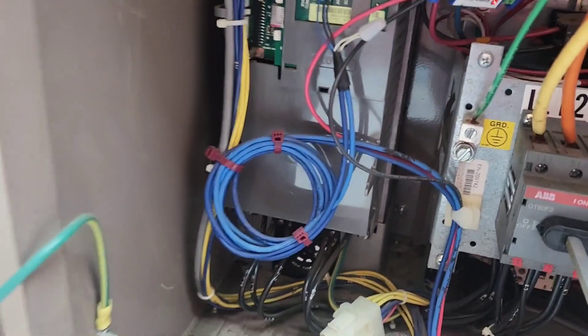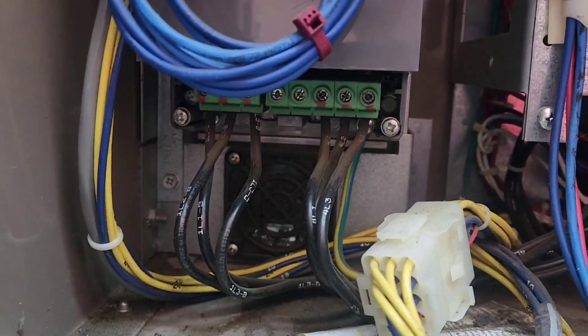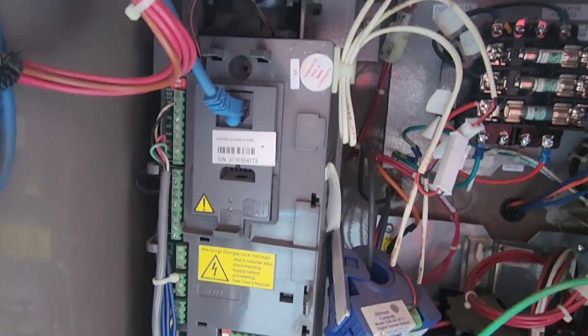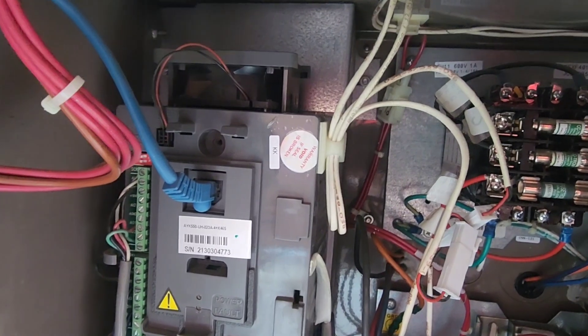Inside here with this particular drive, there's a total of two fans. You've got one right back there, and you have another one that is on the top of the drive itself, and you've got to make sure that the function of both of those is working.